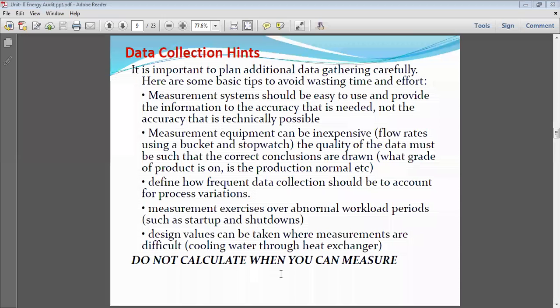If you are able to measure any data, it may be input power, current, or power factor, because calculated data is based on standard formulas, whereas we are not considering different parameters such as harmonics in the system, distortion, or unbalanced voltage, which cannot be calculated. Therefore, during the detail energy audit, we should measure the data as much as possible for a fruitful conclusion.